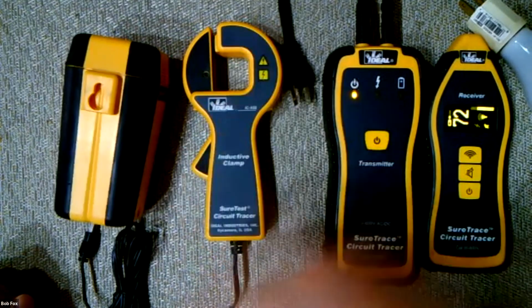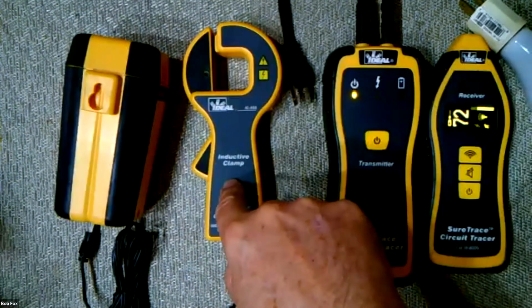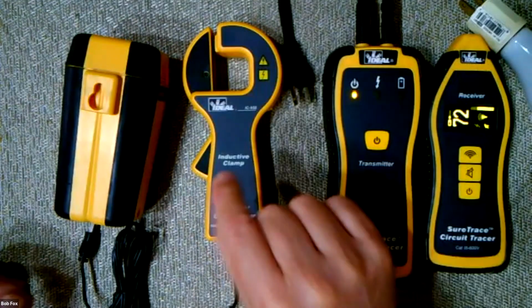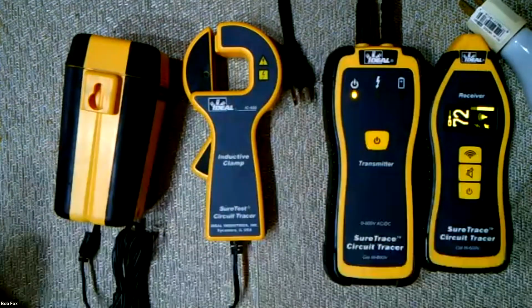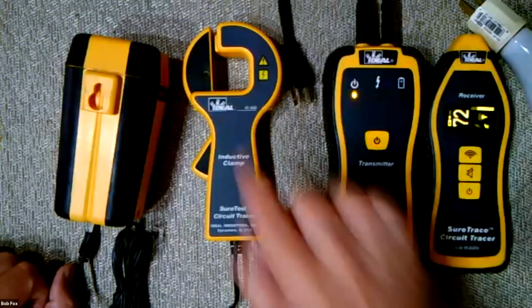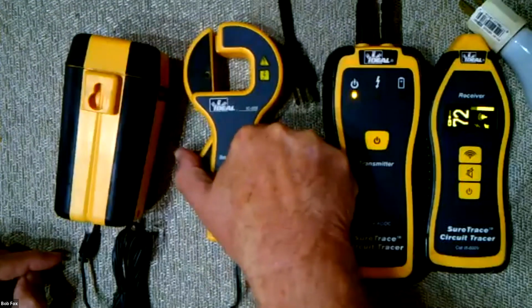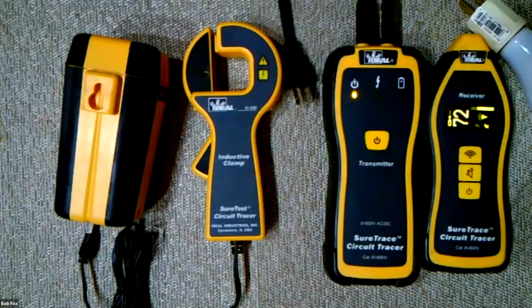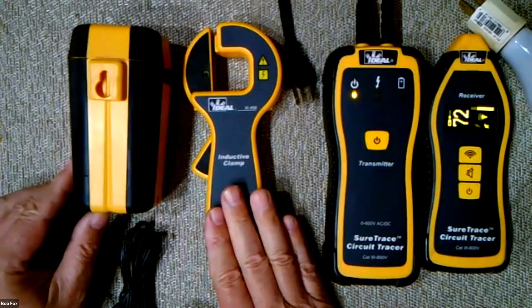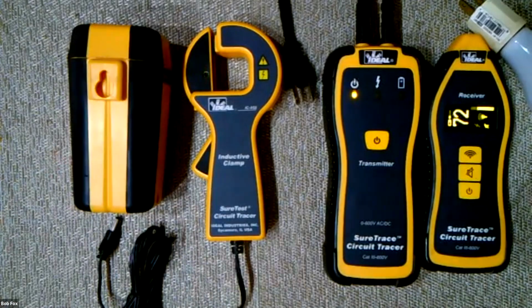Every time it chatters with that 60 hertz waveform that we deal with here in the United States, it opens up at a microscopic level, and every time it opens up, the signal bleeds off. So it's counterproductive to have this opening up at a high frequency when you're trying to induce a signal onto a conductor. That's why its limitation is simply, like we keep saying, 120 volts and 5 amps. I hope that answered the nature of the question.